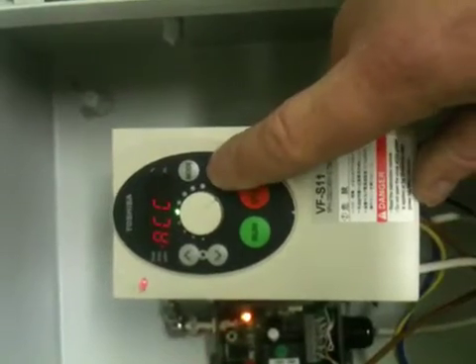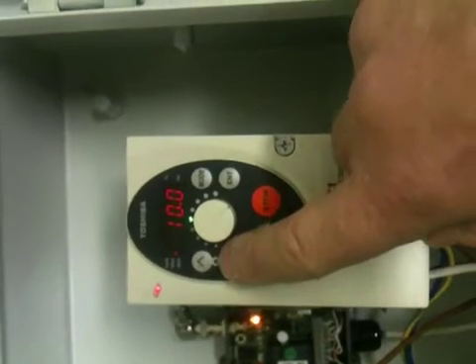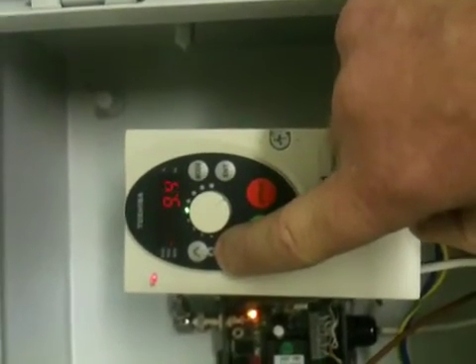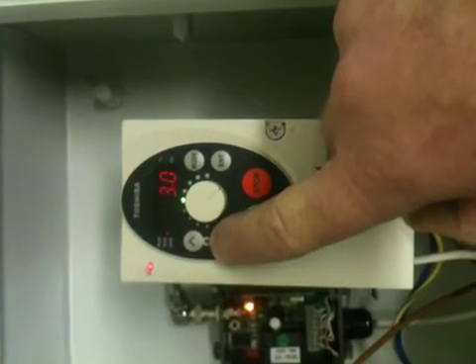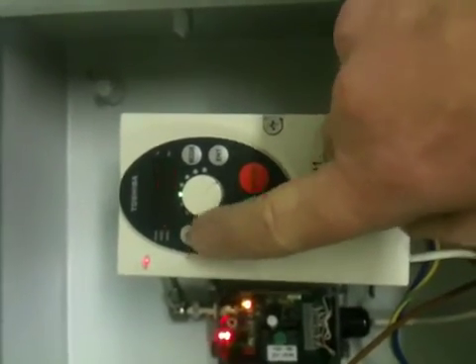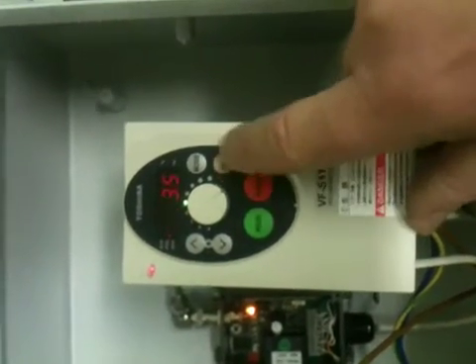Factory default for acceleration is 10 seconds. Hit enter to find the 10, scroll down, reduce it to 3.5, and hit enter to save that. So we have changed ACC, and then go up the menu again to DEC.